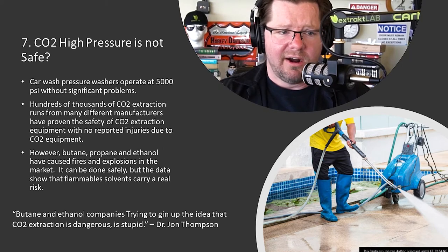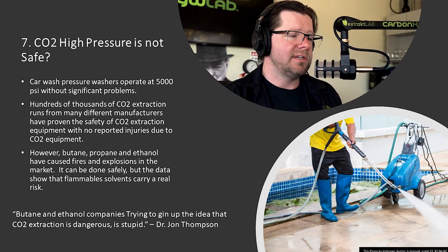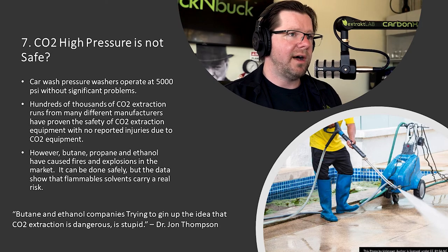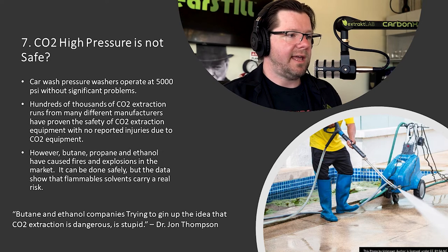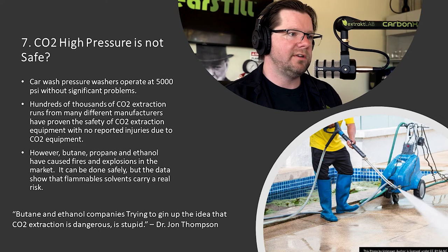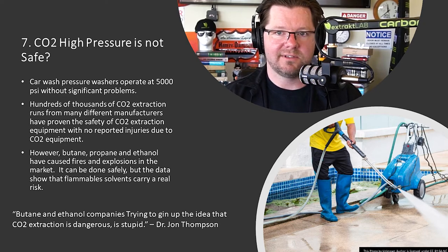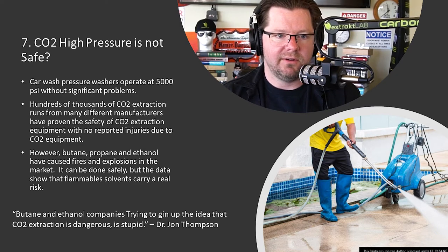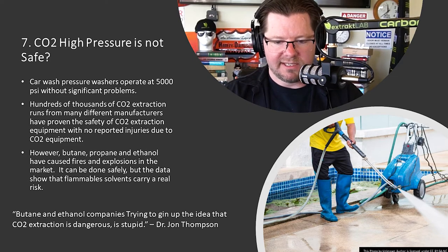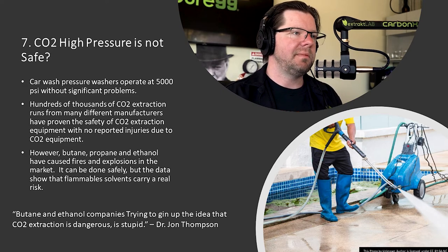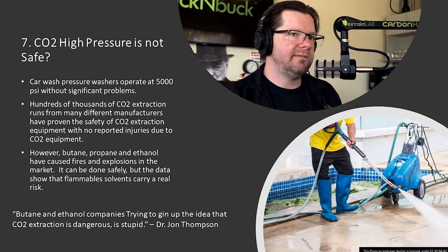There are a lot of CO2 companies and it's used industrially — lots of people use CO2 and the equipment is quite safe. There have been instances of asphyxiation where people left CO2 running and suffocated, but not in our industry. You can check OSHA for those cases. You have to make sure CO2 is handled safely — use alarms, which we have on all our equipment. If there's a leak, the machine shuts off. Our CO2 cages have a vent with a contact closure — if CO2 exceeds 5,000 ppm, a fan turns on and vents it.